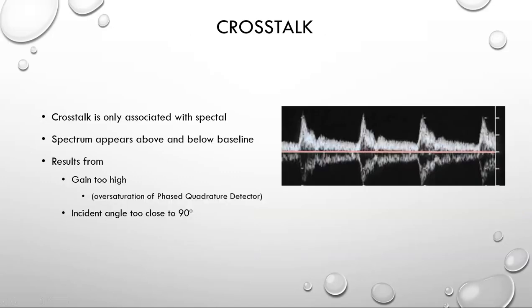Crosstalk is another Doppler artifact associated only with spectral Doppler, where the spectrum appears both above and below the baseline. This results from too high of gain, oversaturation of the phase quadrature detector, or trying to obtain a Doppler angle too close to 90 degrees.